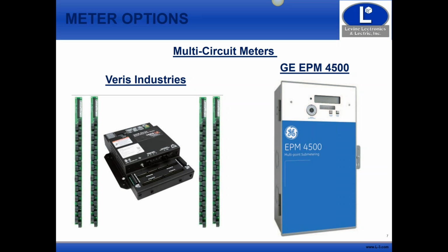Okay, so the EPM 4500 on the right, from GE, typically can be used in a main switchboard, where this meter itself will meter multiple branches within the switchboard. The Veris Industries unit on the left is from a smaller panel board standpoint. So we'll go in a 42 circuit panel, and on the left and right here, these are installed in the panel board. So this is all done at the factory when it's being built.